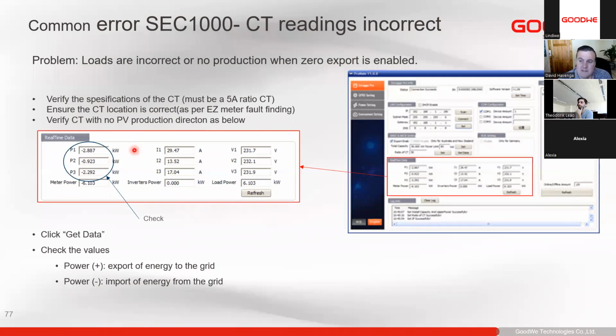Same with our smart meter, if your voltage sense is not the same as the CT input, that can also result in reading out of step, which is reading at a very bad power factor. So just double check your voltage input. This should normally be no more than 20% variance. In European countries, I think we're at 0.9 most of the time. In Africa and those places, sometimes it can be 0.8, depending on the equipment running on the site. But normally no more than 20% variance on the power factor.